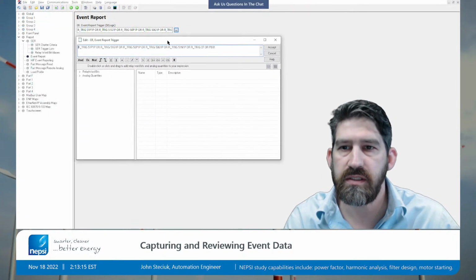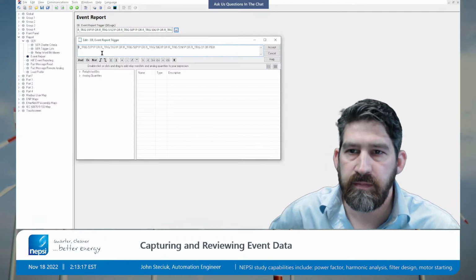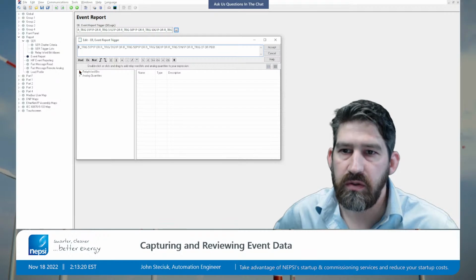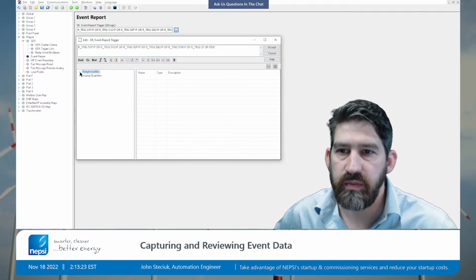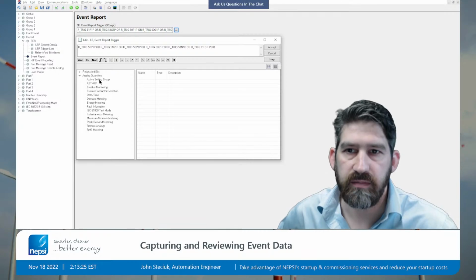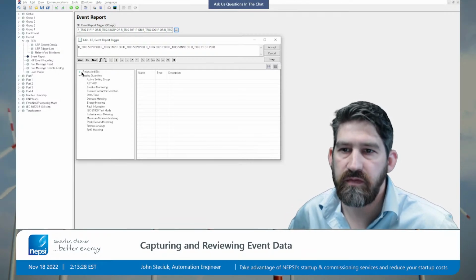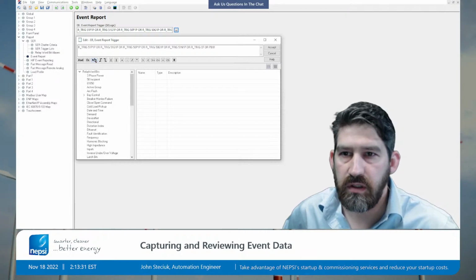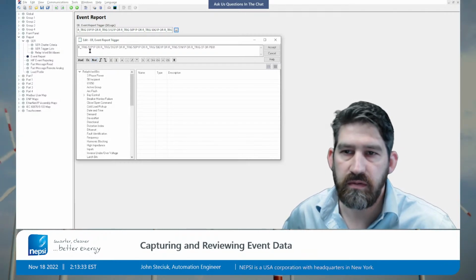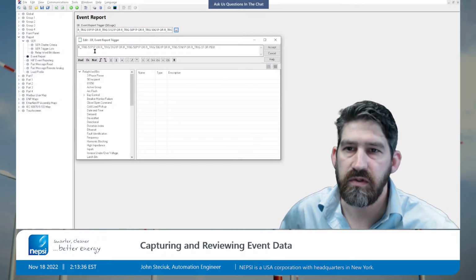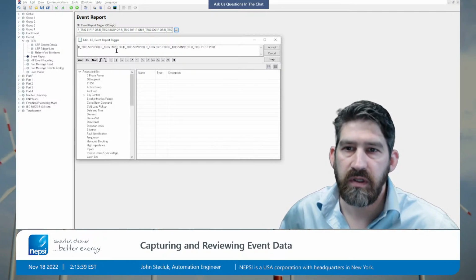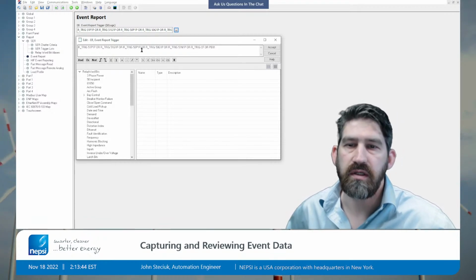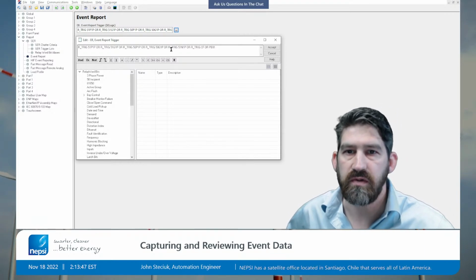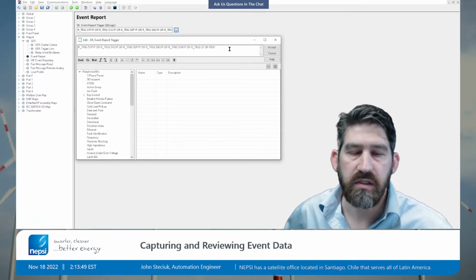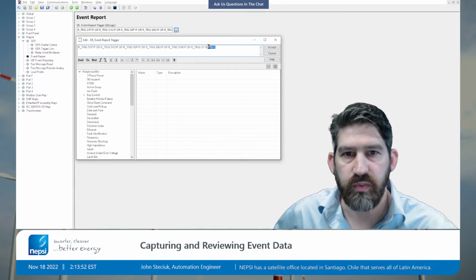If you click on the ellipsis, you can see the setting field here, and down below you've got the available relay word bits or analog quantities that you can log in an event, you can use to trigger an event report. So right now we have a list with pickup values for inverse time over current, inverse time residual over current, and some pickup values for instantaneous over current, and some others. I also have one for push button 1.